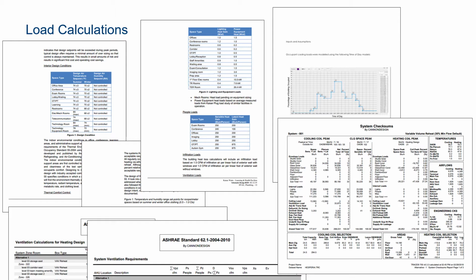So that's why we're very interested in, let's take these calculations that we're getting out of our systems and calibrate them back to reality as often as possible. Water tanks are another funny example. If you're sizing a water tank for 72 hours of water, do your calculation, but then take a look at some bill data, right? Check it against reality and ask us because we have that bill data, or ask our facilities engineers because they have system data, we have trend data, and we want to share it with you and make those designs smarter.